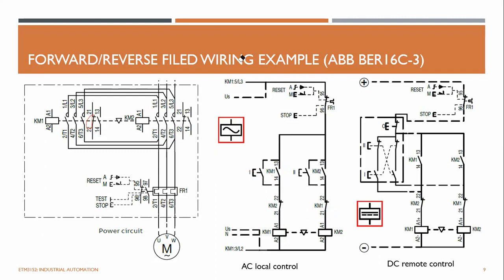Same thing happens here. When this side is energized, when KM2 is energized, the KM2 normally close contact put here means KM1 is not allowed to energize at any time, because this is disconnected. When KM2 is operating, the KM2 normally close contact put here gets opened and does not allow KM1 to energize at any cost. Which means the electrical interlock is also there for redundancy and as another layer of protection.